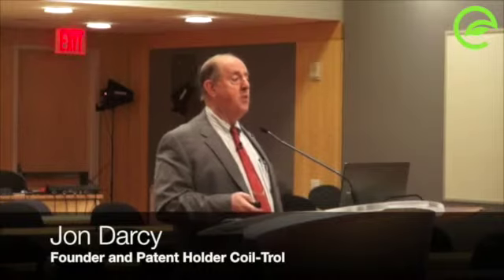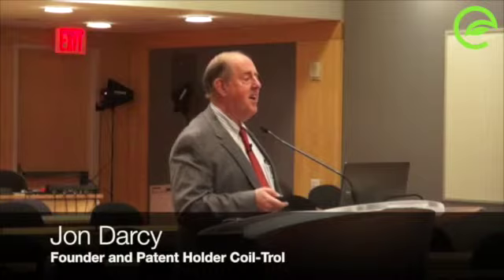So when the temperature goes down, the relative humidity goes up. If you lower your chill water temperature and get your discharge air temperature down, the relative humidity goes up, which then calls for the chill water to be lower. And so it's an endless cycle. It's a Foo-bird loop. Foo-bird is defined as a bird that flies in increasingly smaller circles until it flies up its own ass. Anyway, trying to control from relative humidity is a Foo-bird loop.